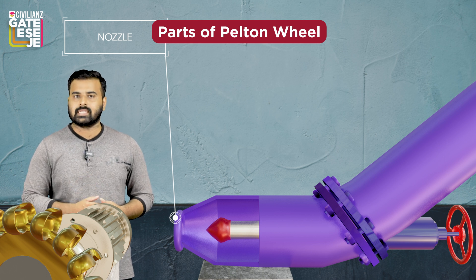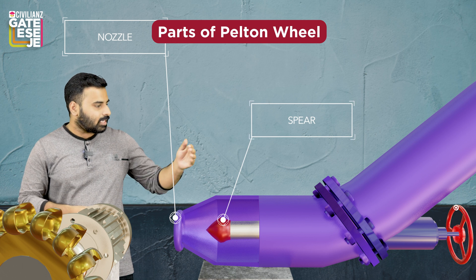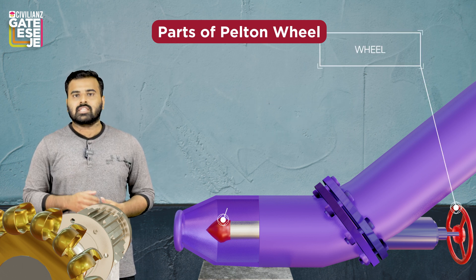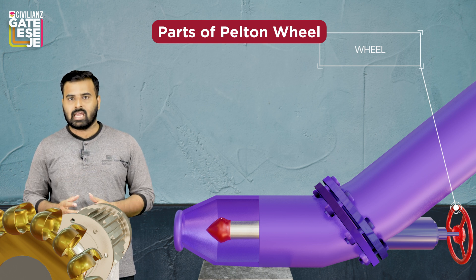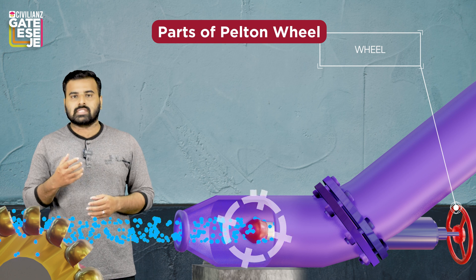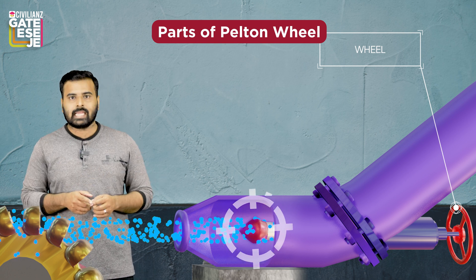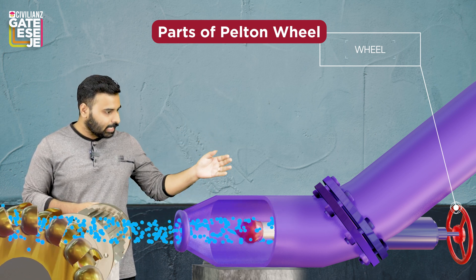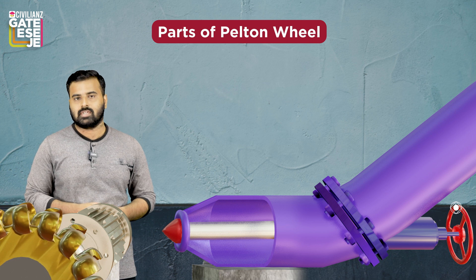The second important part is the nozzle. Its main function is to ensure that the total energy at the inlet of the Pelton wheel contains only kinetic energy. The next part is the spear and the wheel. The main function of the spear is to regulate the flow properly through the nozzle — as the spear moves to and fro through the nozzle, the flow is controlled. The to-and-fro movement of the spear is controlled by the wheel.